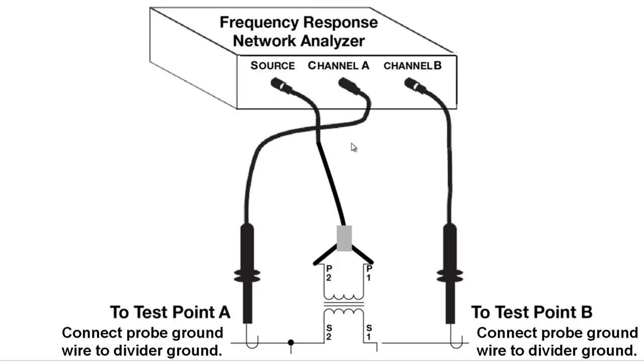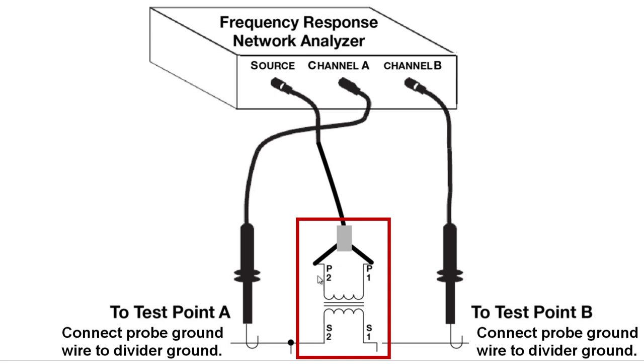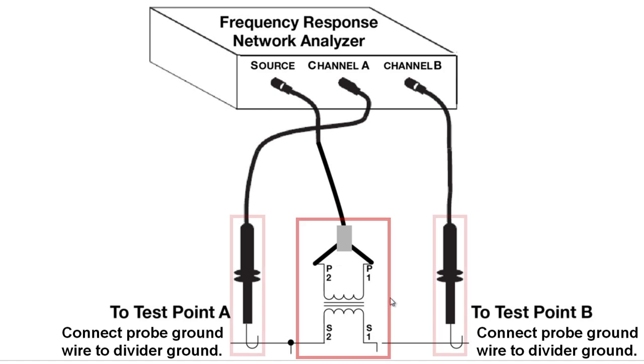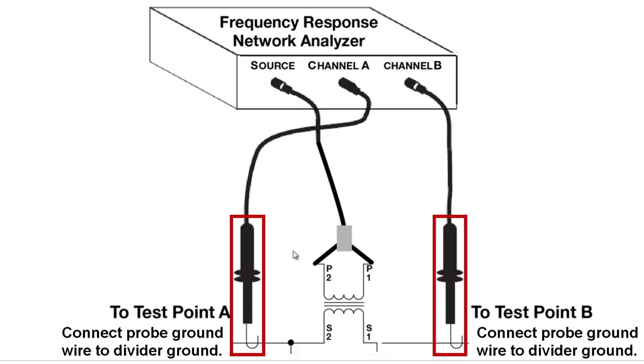For the testing, the equipment will have an output that will be driven into an isolation transformer. The isolation transformer is there so that there's no DC bias point that could either disturb the measurement itself or cause damage. And then two points that come back up, receiver points that come back up into the equipment.